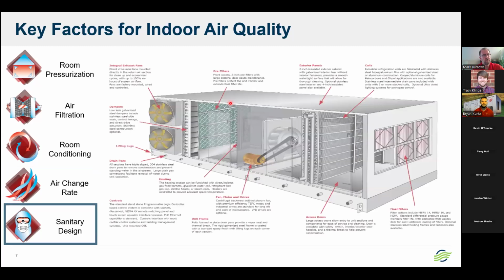And then, of course, this overall sanitary design. In a perfect world, we'd love to see stainless steel everything. That's the most hygienic you can get. That being said, we also understand that budget reasons may not allow for that. So we do have some other lesser hygienic options that help from a budgetary standpoint, but ideally, you're looking at stainless steel dampers, interior liners, and certainly drain pans, which are standard throughout the entirety of our unit. So it's not just post-coil like you might see with some manufacturers. We do put stainless steel drain pans through the entire unit.